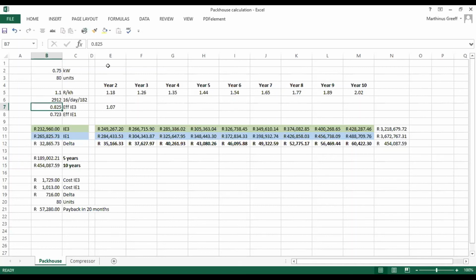Then I looked at these two motors at their efficiency rating. The IE3 would be 82.5%, and the standard efficiency would be 72.3%, so we see a big jump in efficiency. What I basically did here is calculate how much it would cost to run that motor over the same period. The IE3 would cost us 232,000 Rand, the IE1 would cost 265,000, and the savings would be 32,000 Rand per year just from changing 80 of these motors in one packhouse.